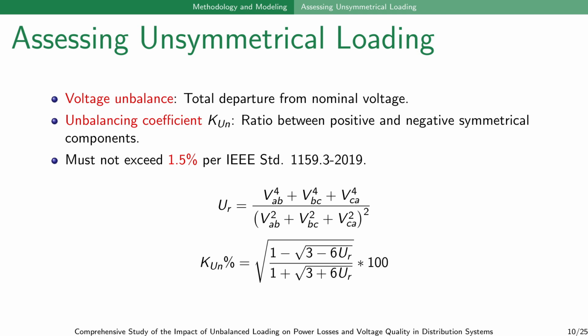Assessing unsymmetrical loading involves calculating the voltage imbalance defined as the total departure from the nominal voltage. The imbalancing coefficient is the ratio between the positive and negative symmetrical component. According to IEEE standard 1159 for the year 2019, this coefficient must not exceed 1.5%, and the equation how to calculate the unbalanced ratio is presented here.